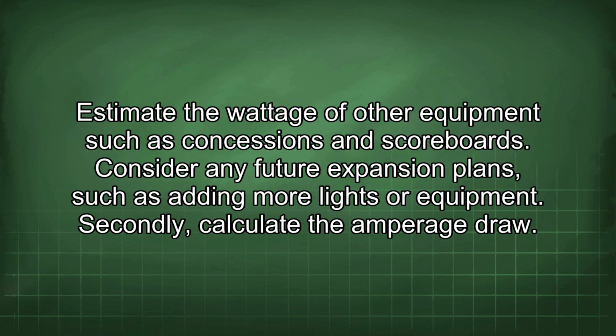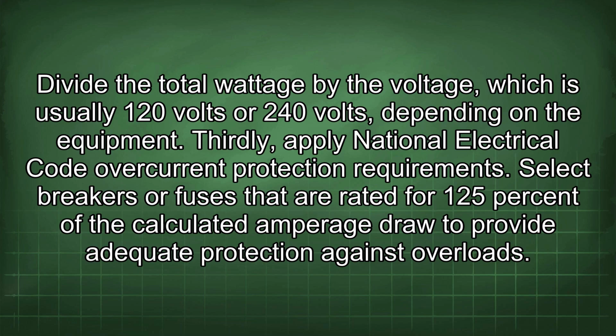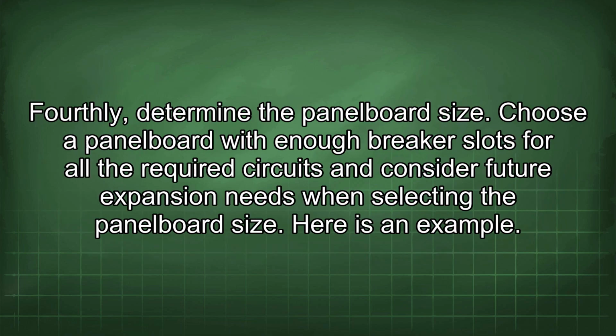Secondly, calculate the amperage draw. Divide the total wattage by the voltage, which is usually 120 volts or 240 volts, depending on the equipment. Thirdly, apply National Electrical Code overcurrent protection requirements. Select breakers or fuses that are rated for 125% of the calculated amperage draw to provide adequate protection against overloads. Fourthly, determine the panel board size. Choose a panel board with enough breaker slots for all the required circuits and consider future expansion needs when selecting the panel board size.